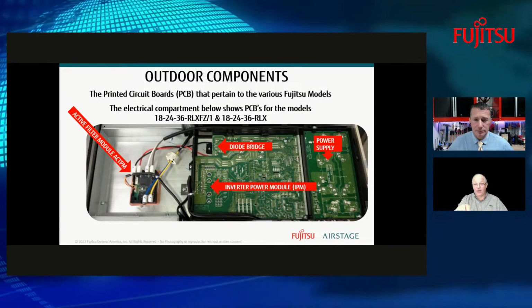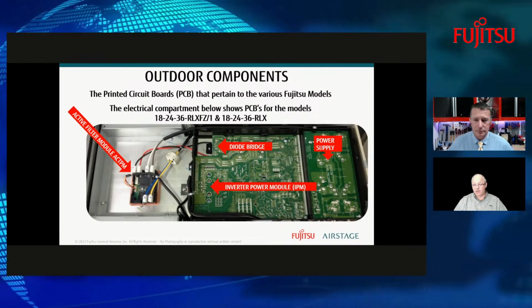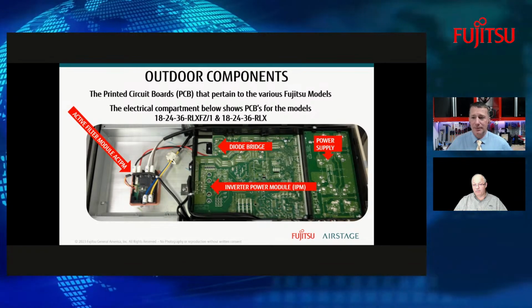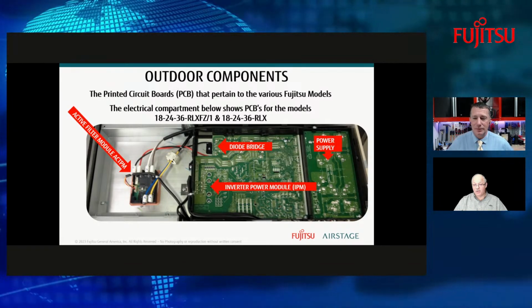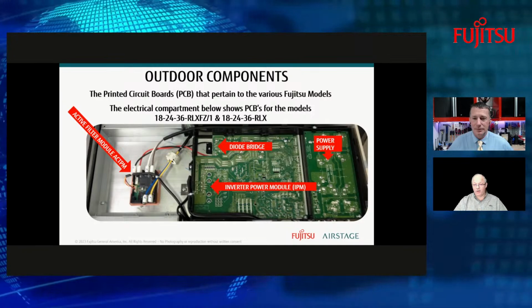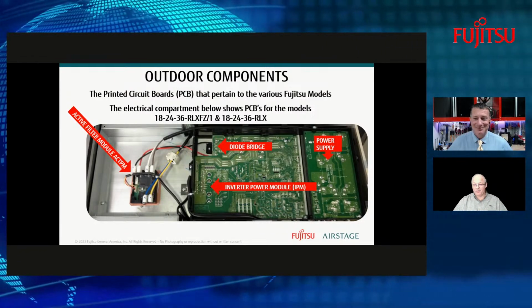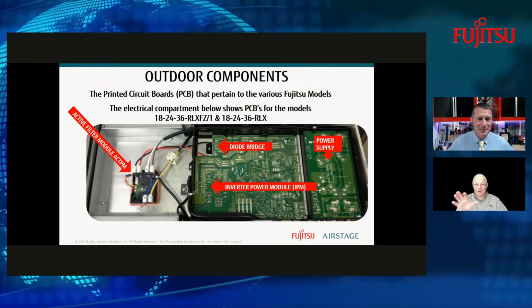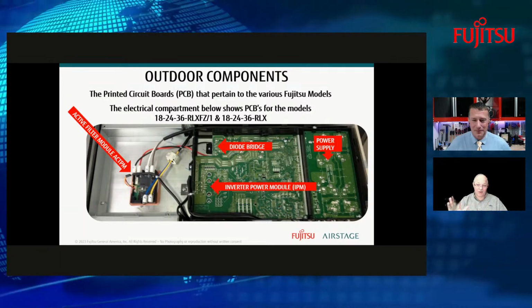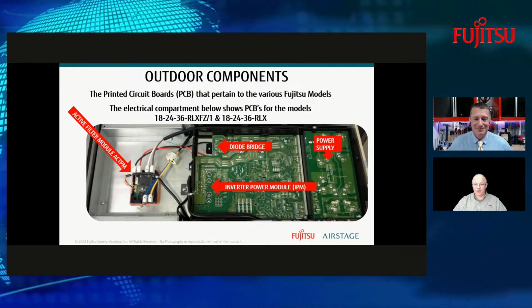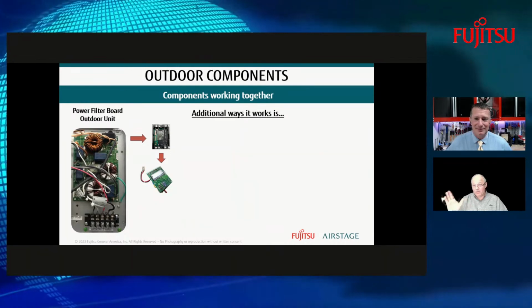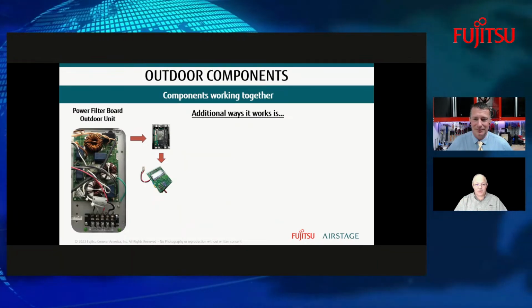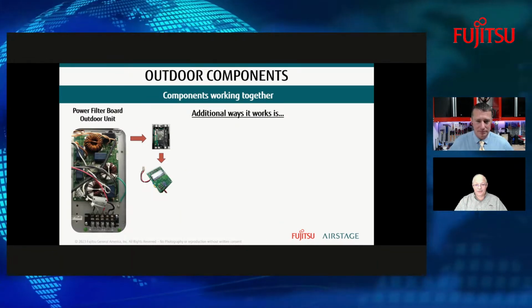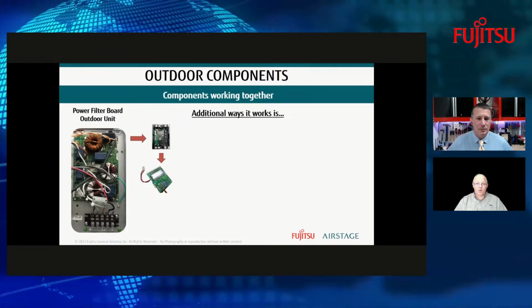So I can tell by looking at this one, just because it's all one big board there in the center, I know that is a multi-zone system. And how is that? Because if it was a single zone, it would have been that little smaller square board that we showed you earlier. Ah, okay. So if you just walked me up to it and didn't let me look at a model number, I could just look at that board and know you got one of our multi-zones, whether it's a dual or a tri. So there are some additional ways that this works.